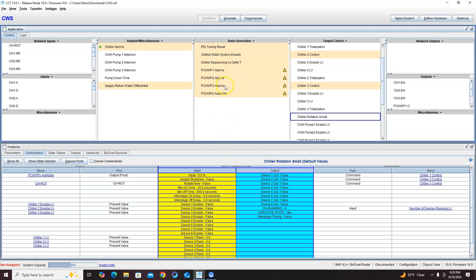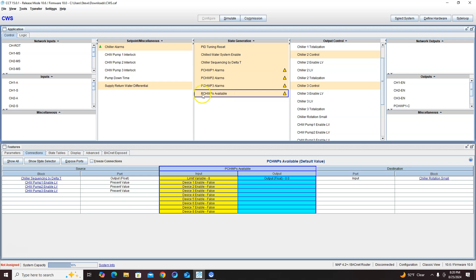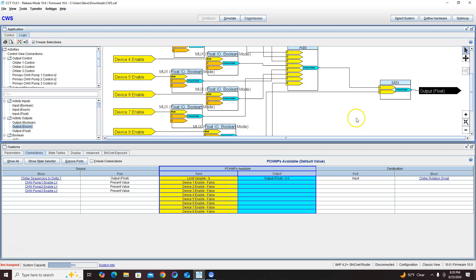But I got three pumps, I only want a maximum of two chillers to run. That's no problem, all you have to do is come in here and view this logic. Add another minimum right here.